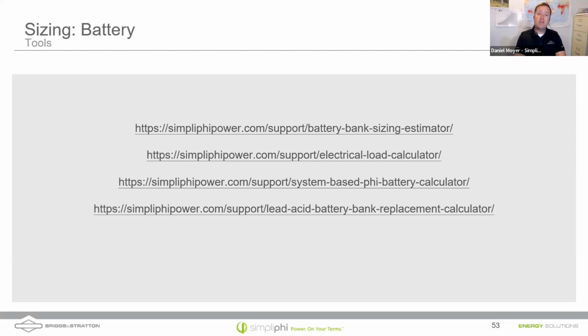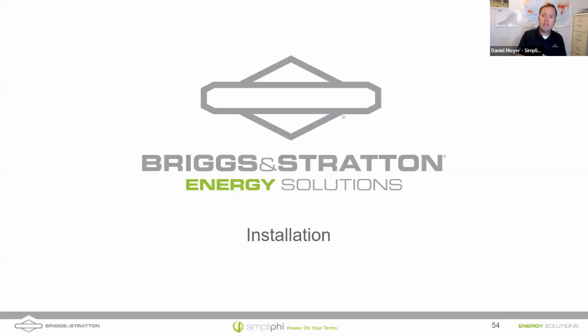Sizing these energy storage systems, especially for grid-tied interactive systems, is complicated. A lot of people want to size to the backed up loads, but really we should be sizing to what we expect time of use arbitrage to be. Or if we're in a net metering situation, we're thinking about sizing to that component, not necessarily sizing to what somebody is going to expect for an outage.